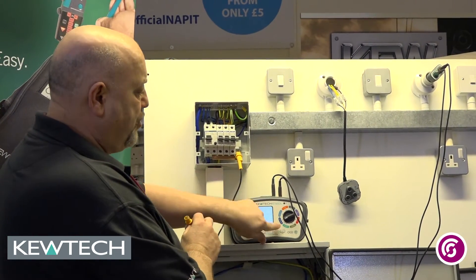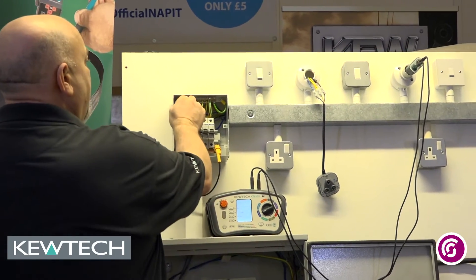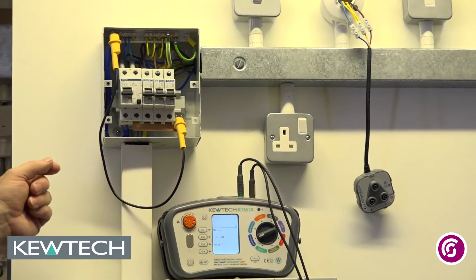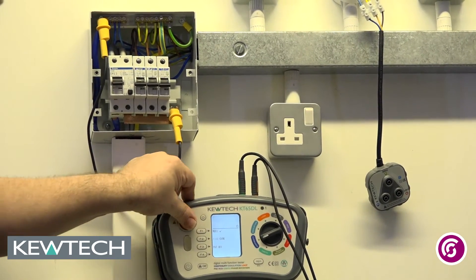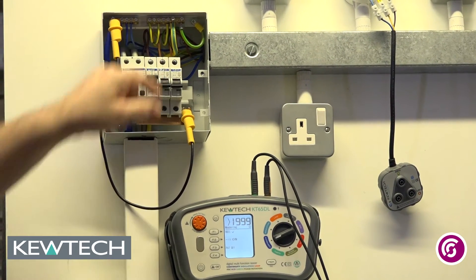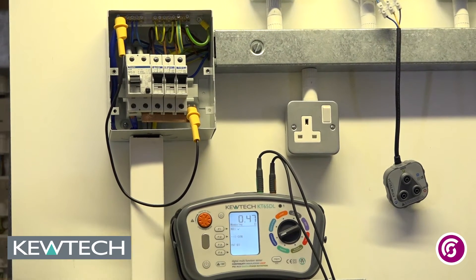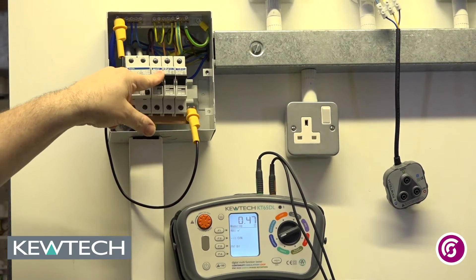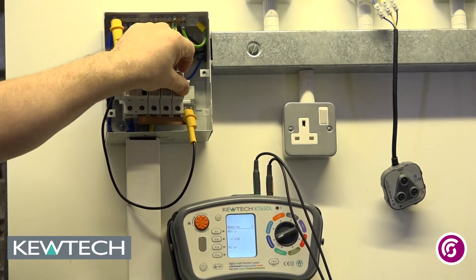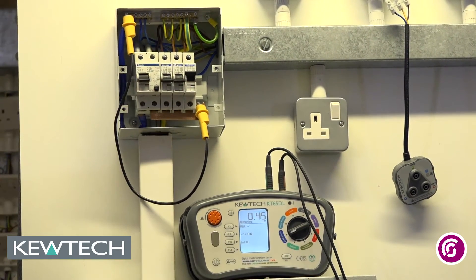So what I want to do — it's on continuity and I'm linking between the R1 busbar and the RN neutral bar in the consumer unit. If I now push and twist it's in constant testing mode and as you can see I've got no circuit. If I turn the circuits on one at a time, or in fact if I turn them all on and I get a reading I know I've got a circuit. All I have to do is turn them off until I break the circuit. So that point for R1, RN is on circuit number 3.